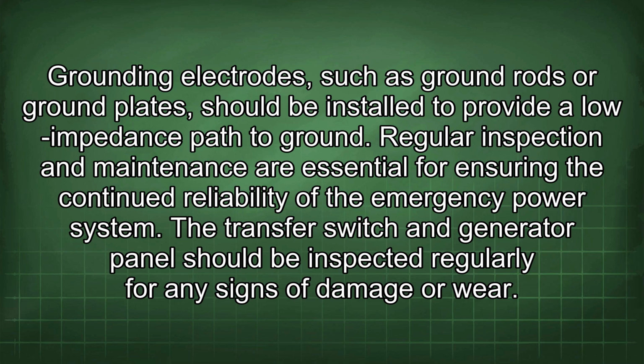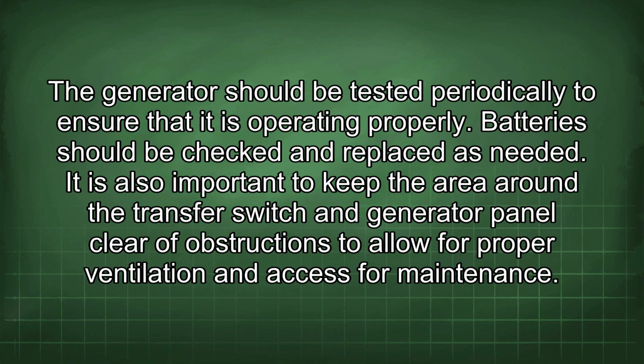Regular inspection and maintenance are essential for ensuring the continued reliability of the emergency power system. The transfer switch and generator panel should be inspected regularly for any signs of damage or wear. The generator should be tested periodically to ensure that it is operating properly. Batteries should be checked and replaced as needed. It is also important to keep the area around the transfer switch and generator panel clear of obstructions to allow for proper ventilation and access for maintenance.